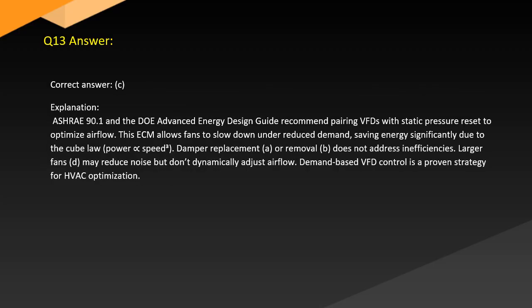Answer. Correct answer: C. Explanation. ASHRAE 90.1 and the Advanced Energy Design Guide recommend pairing VFDs with static pressure reset to optimize airflow. This ECM allows fans to slow down under reduced demand, saving energy significantly due to the cube law, power equals speed cubed.